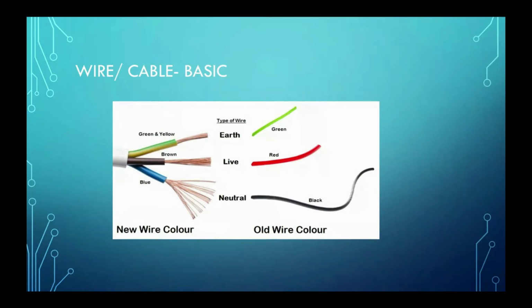So first of all, some of you may not know what is earth wire, what is live, what is neutral. Never mind, I start from basic. Previously the old wire color code is green is earth, red is live, black is neutral. Now the standard changed to a new wire color code: brown is live, blue is neutral, earth is green-yellow.